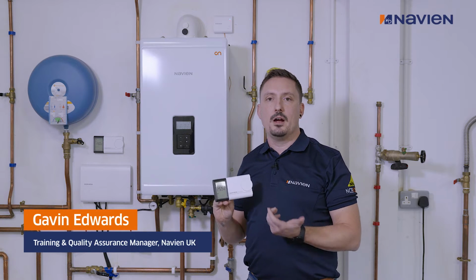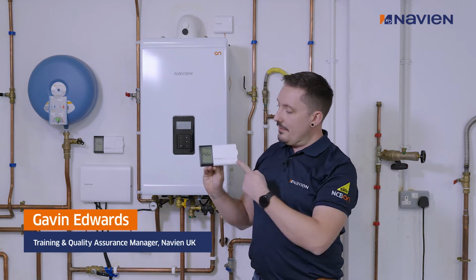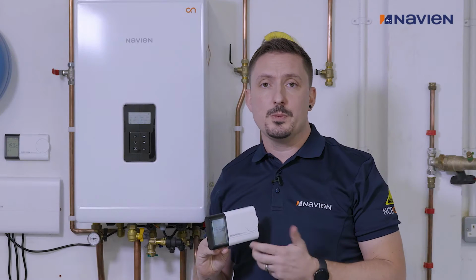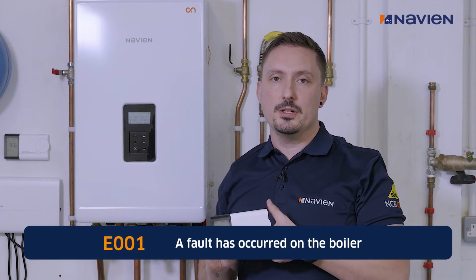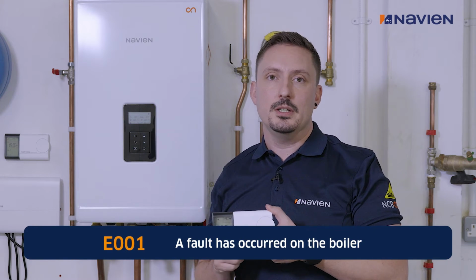So in this scenario, I'm going to briefly go through what error codes you'll see on our Navien Smart Plus. The first one being E001. That means a fault has occurred on the boiler, but doesn't have any relevance to the fault code on the boiler. So you'll need to go to the display to check what the fault code is.